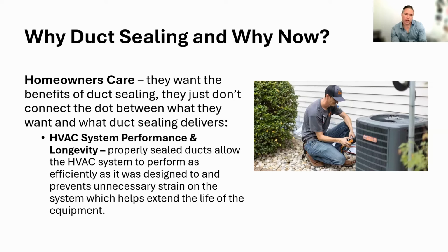And then in addition to that, it's everything that we talked about. If you don't seal the ductwork, another angle on this is we're pulling potential contaminants not only into the house, both through the supply and return, mind you, it's not just the return, but also you're pulling potential contaminants into the furnace. Right? You have a filter in front of that furnace, but it doesn't stop everything. So you will introduce more contaminants to the fan and build up dust and dirt in that fan quicker without properly sealed ductwork. And it will cut down your need to clean that ductwork tremendously. There's a number of reasons why it's important, but all of this will affect that.